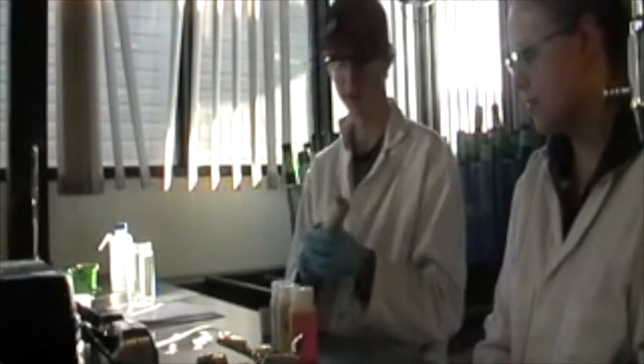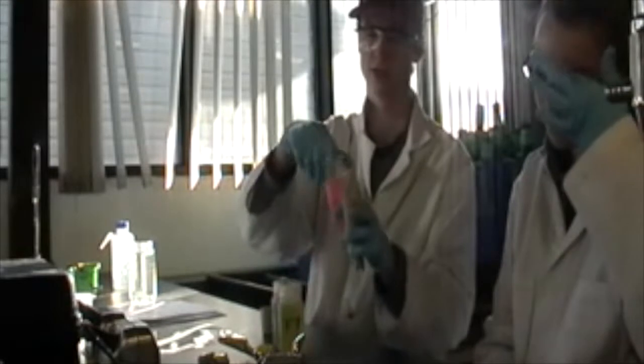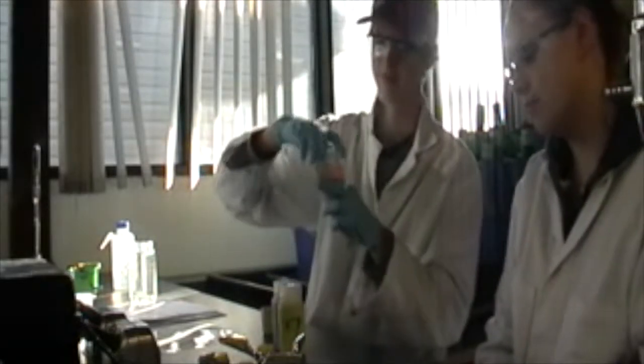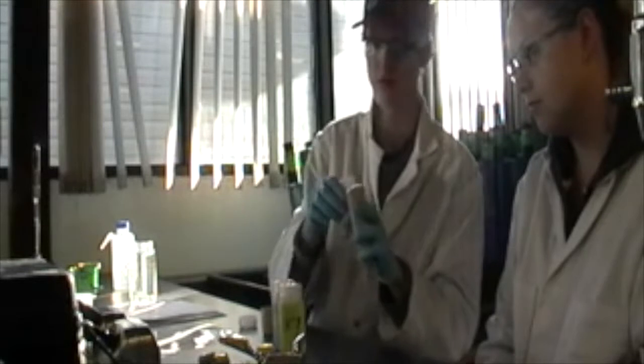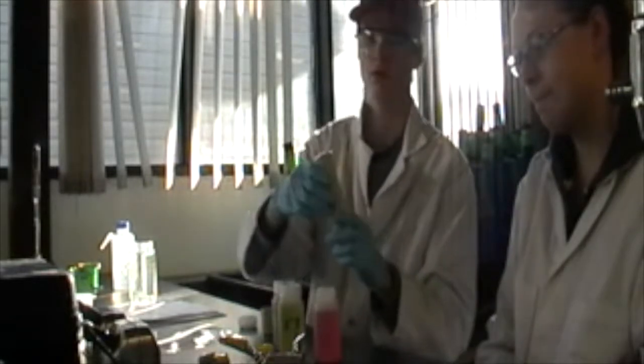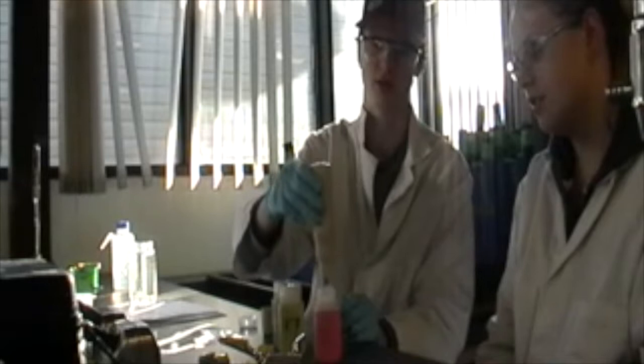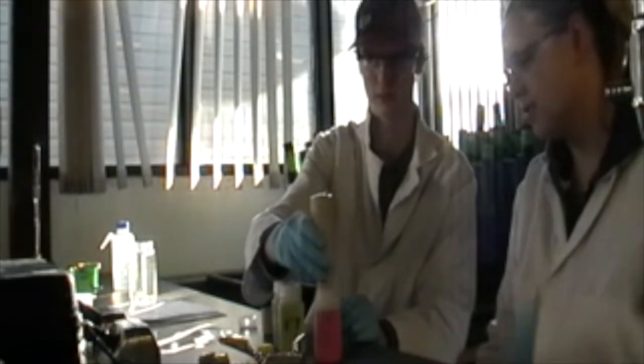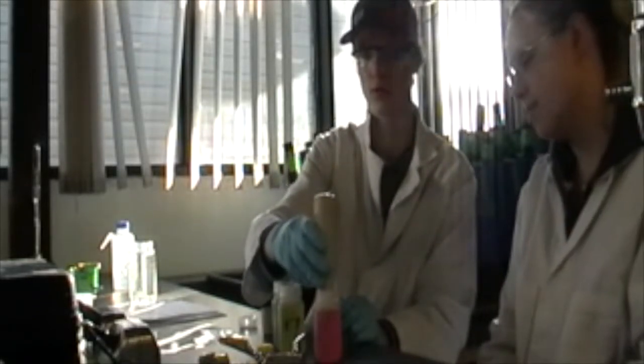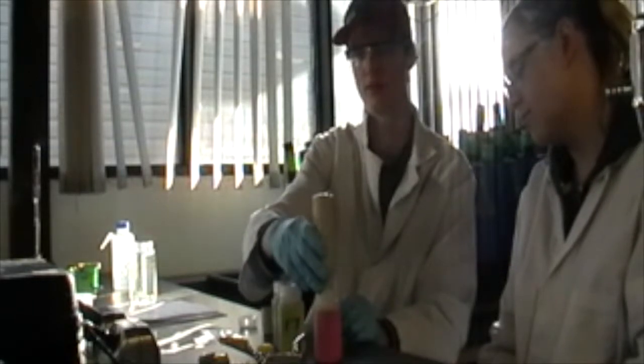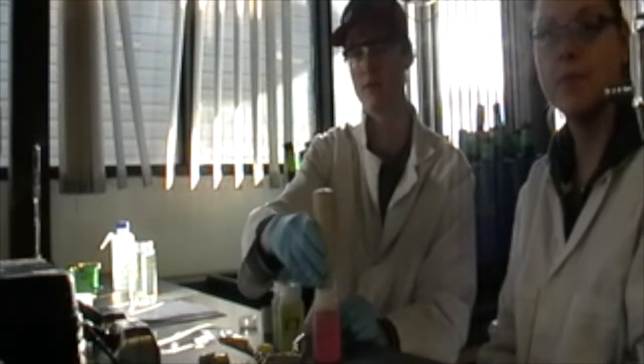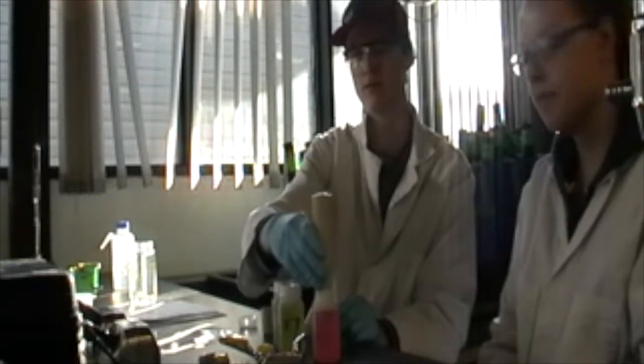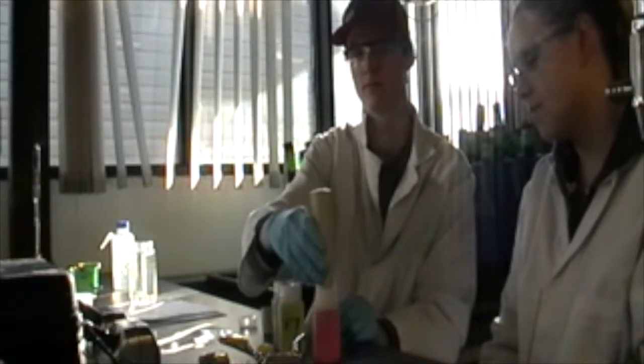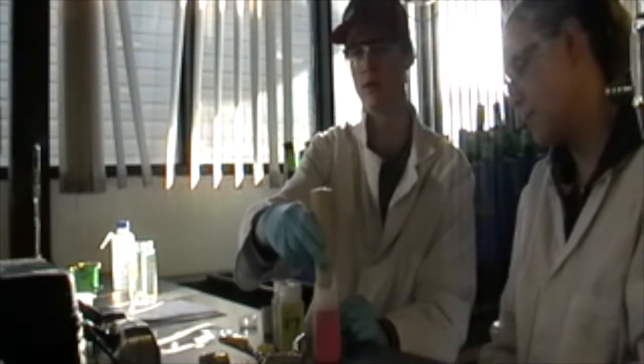The first known pH solution we're going to start off with for the calibration is the pH of 4. We're going to put our probe into the pH of 4 and hit calibrate. We're going to wait for a few minutes to let the pH stabilize. Once stabilized, we will click hold and then calibrate in the known pH solution of 7.